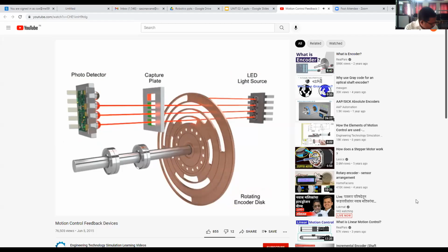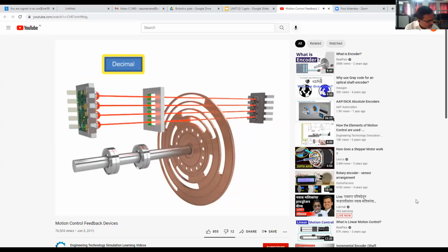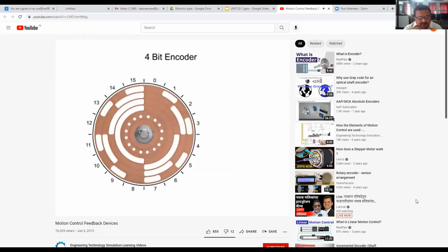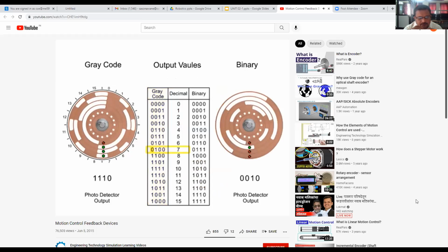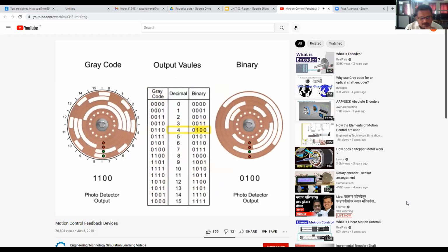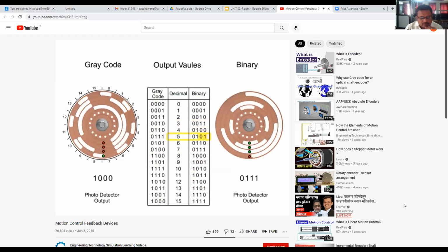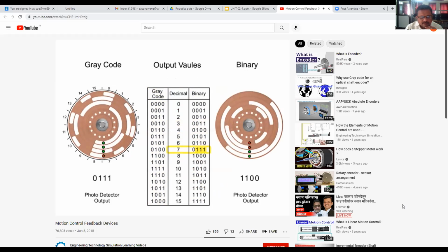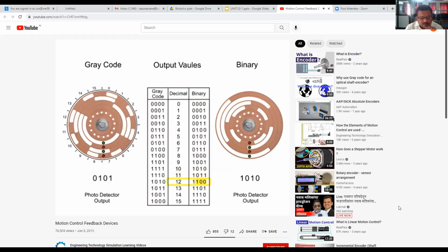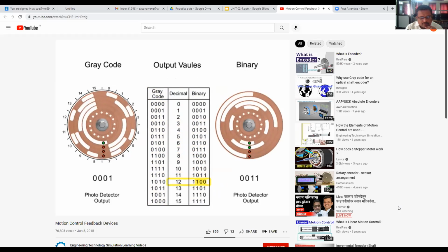The most common types of numerical encoders are decimal, binary, and gray code. In a 4-bit encoder, there are 16 unique combinations for numeric code every 22.5 degrees. Gray code is designed where only one bit changes at a time, contrary to a binary system where one or more numbers change in the word. By changing more than one number of the word at a time in the binary system, the possibility of positioning errors is greater, leaving gray code the preference in precision applications.